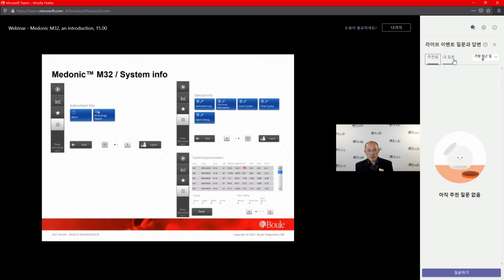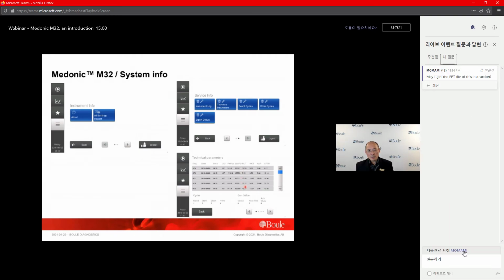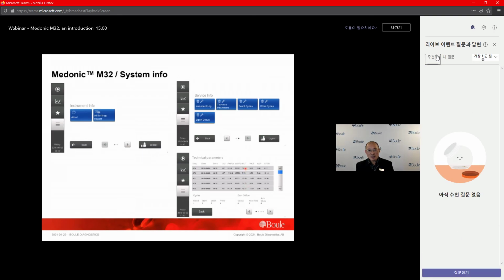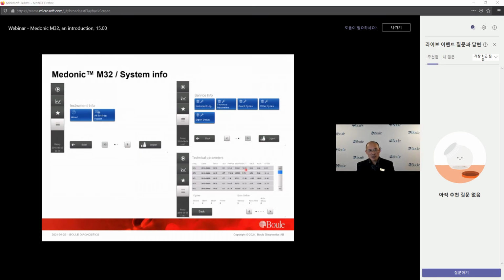The normal range for the counting is quite fixed. For example, RBC is about 13 to 16 seconds. For WBC, 9 to 13 seconds. And if the counting time deviates, it could be a capillary aperture clogging, or the pump providing the pressure could deviate, or the valves or the loop of tubing after the aperture have higher resistance. So these parameters can give us some information regarding the status or health of the instrument.